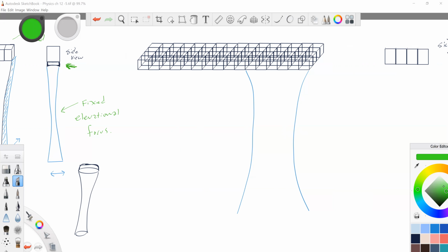But in any case, 1.5D transducers focus in the width and in the elevation electronically. And of course, they steer electronically as well. So they phase in 2 directions, and then they sequence as well. Because you see that I made it sequence by not using the entire row. I only used the last elements here.